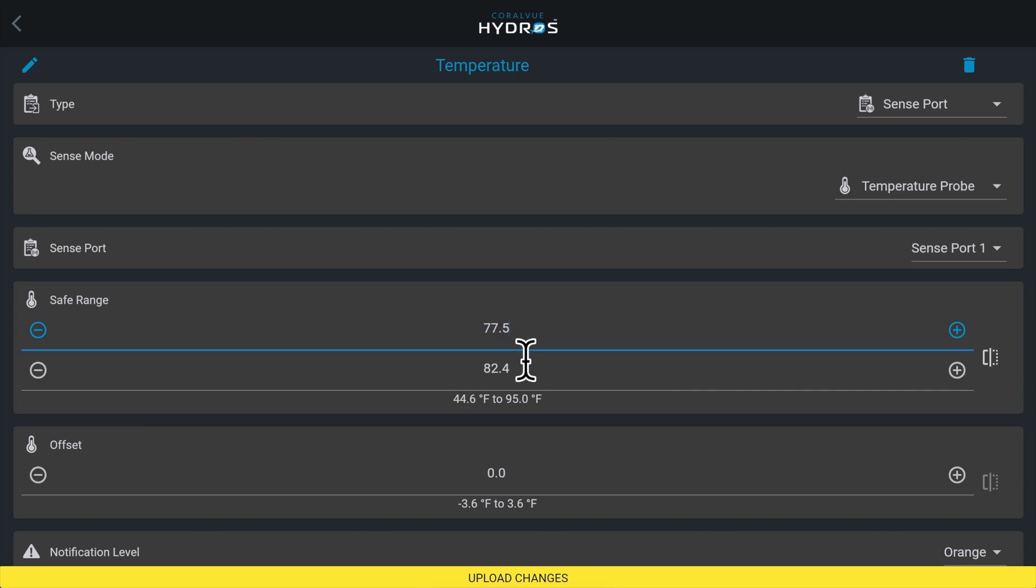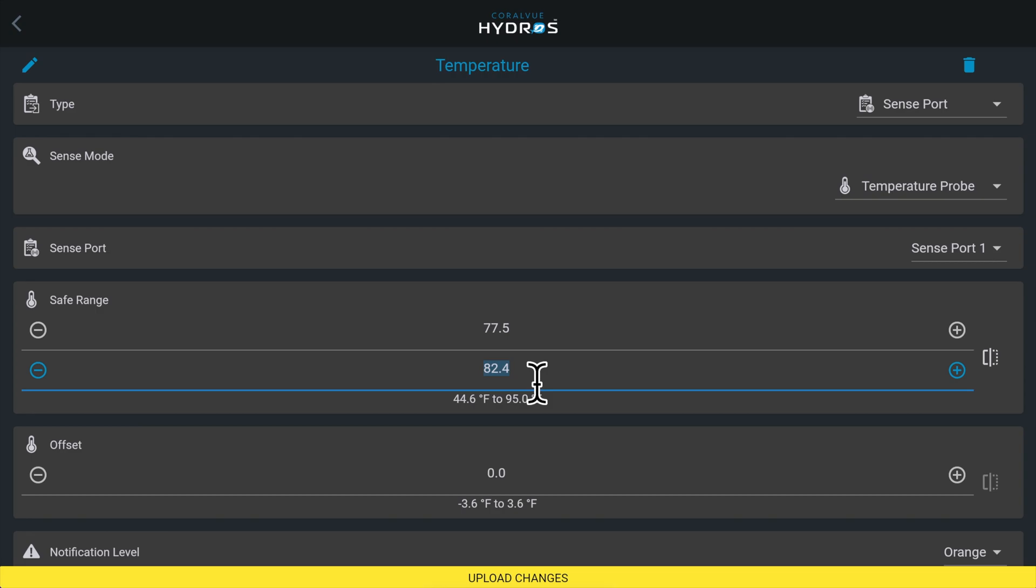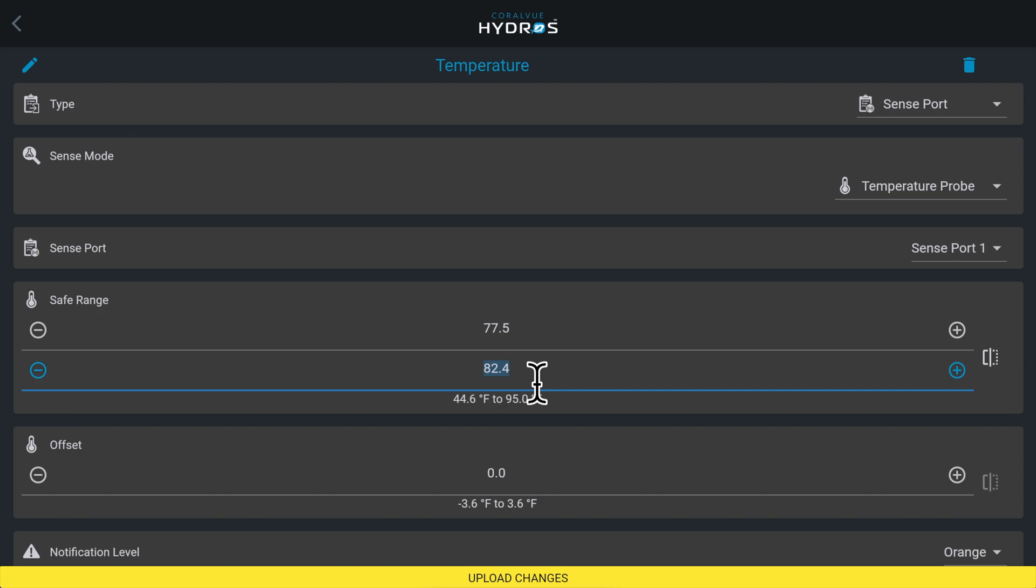Safe range high. This is your maximum temperature. If the temperature surpasses this level, the input icon on the status screen will turn red and a notification will be triggered if enabled below. Remember, this is not the same as the high temperature when the heater turns off. Set this temperature a little higher. For example, if you keep your temperature between 78 and 79 degrees, set this to 81 degrees.